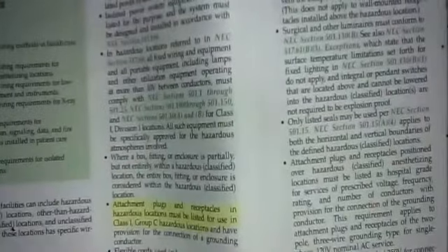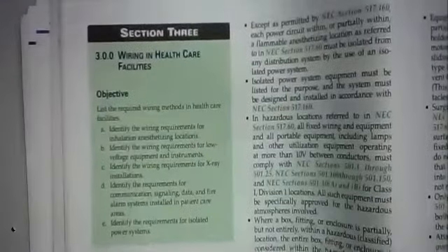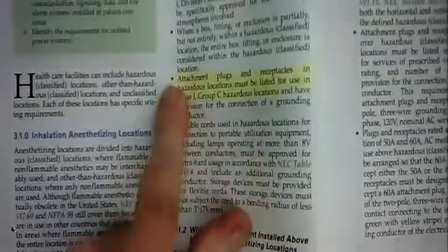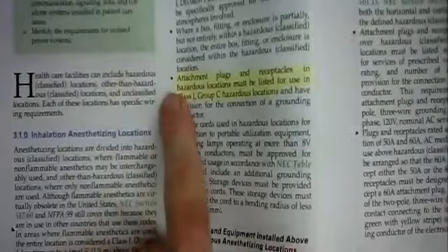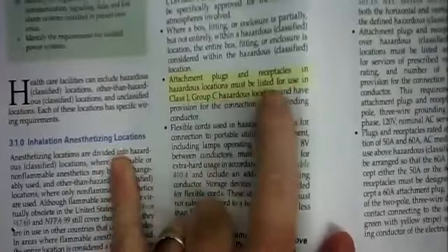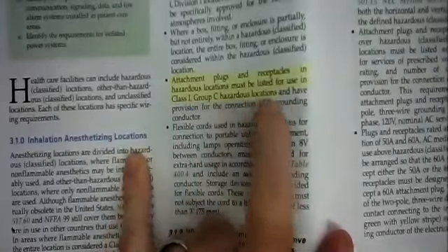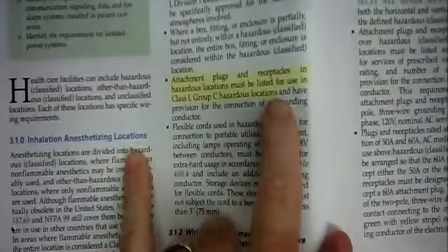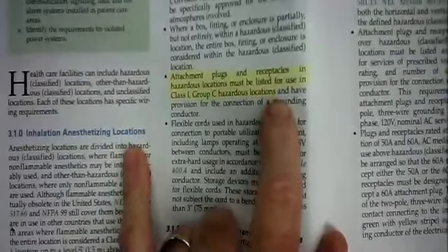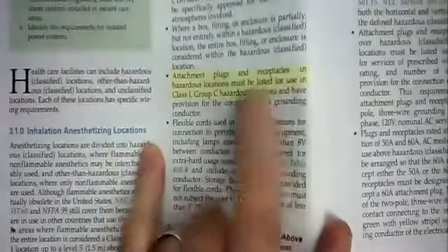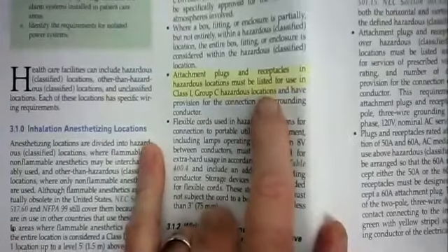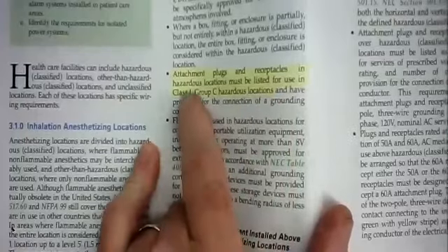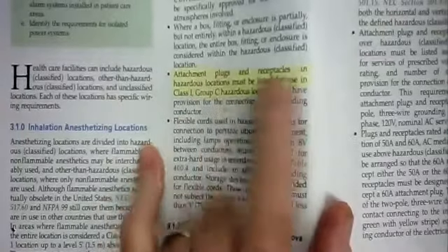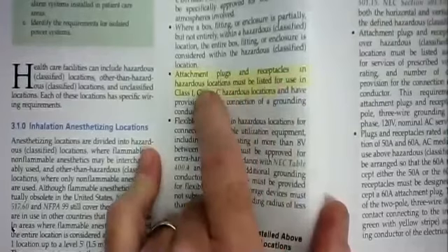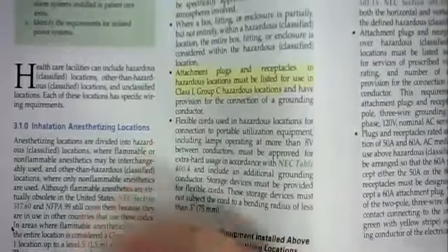Let's take a look at page 18. This is wiring in healthcare facilities. On the right-hand column, 1, 2, 3, 4, 5. The 5th bullet down says attachment plugs and receptacles in hazardous locations must be listed for use in Class 1 Group C hazardous locations. Where would that be? Well, anesthetizing rooms. That chemical that they use to anesthetize you is highly flammable. So if you're using anesthesia, you have to have Class 1 Group C hazardous locations on your attachment plugs, so that they're not going to arc or spark and cause an explosion.